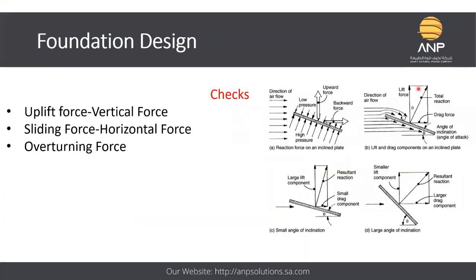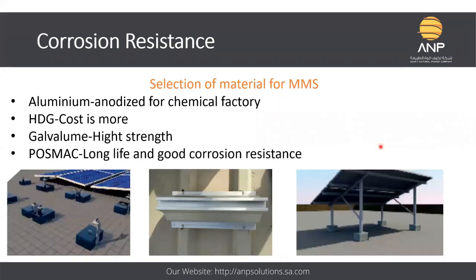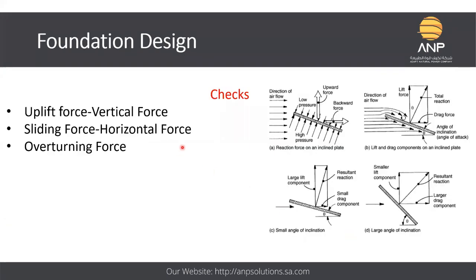Okay. Another point you have to take care about while designing the module mounting structure is various forces: uplift force, sliding force, and overturning force. You have to calculate how much the maximum forces will be. On the basis of this, for example, if your installation is RCC, the foundation dimension will be changed as per these forces. So you have to take care about these forces.